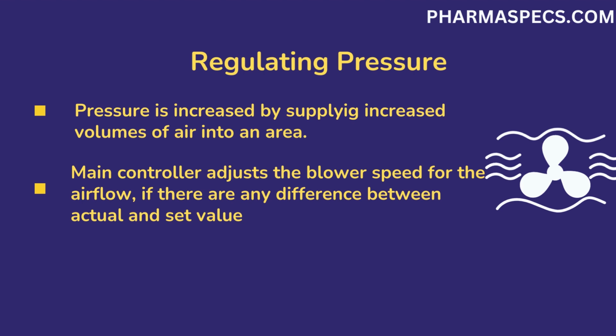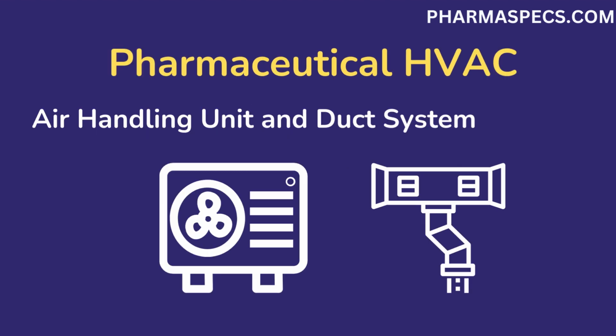In pharma HVAC system, pressure is increased by supplying air in larger quantities. Differential pressure sensors installed in the area calculate the pressure of a specific area with respect to adjacent area. HVAC can adjust the required pressure value if required. Now let's discuss briefly air handling unit and ducting in the pharmaceutical HVAC system. These are essential components of pharmaceutical HVAC. If these two components are not designed and maintained properly, it will negatively affect the entire pharma operation and can damage the serving area's environmental conditions.